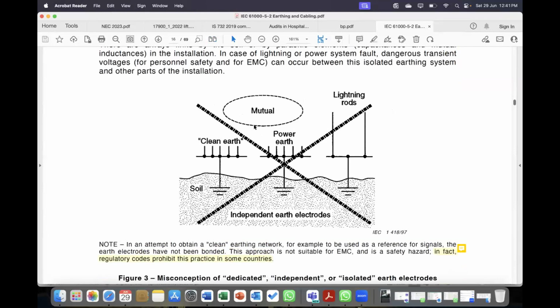That means the method which is followed, the general practice of earthing which we carry out in India, is a mistake. It's wrong. It is like a transformer neutral separate, body separate. This is what we are fighting against. We don't know from where this concept started, as Mr. Bhushan told, during the 1990s. So there was a copper wire running back to the neutral of the transformer. That is the correct system. But nowadays we are going more and more wrong. So you have to make a proper, established network, like a TNS. Thank you.